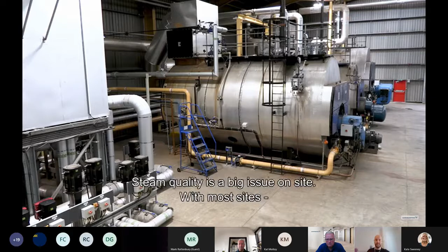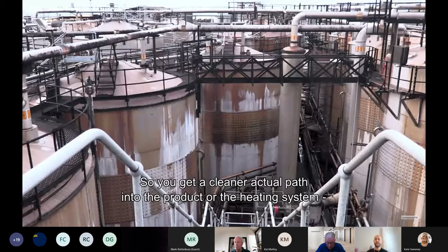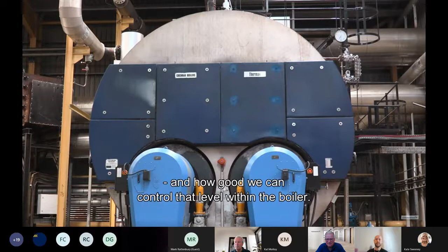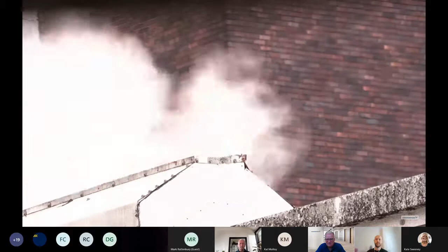One of the problems we see on site is steam quality, which is a big issue on most sites. The better the steam quality, the less water retention within the steam, so you get a cleaner path into the product or heating system and better heat transfer. You don't see as much condensate. This all comes down to level control within the boiler - the better the level control, the better the steam quality.